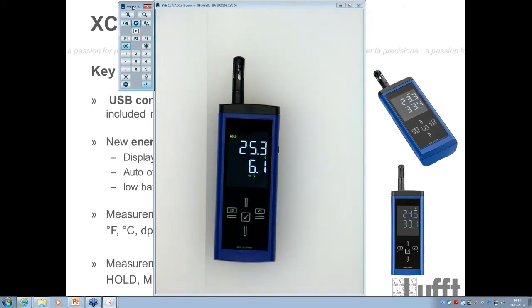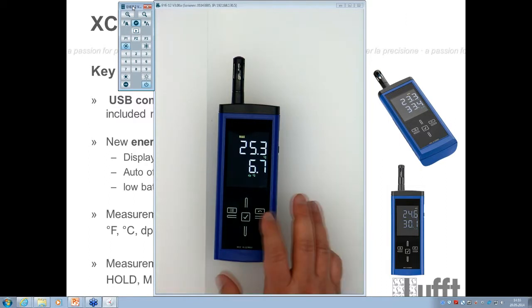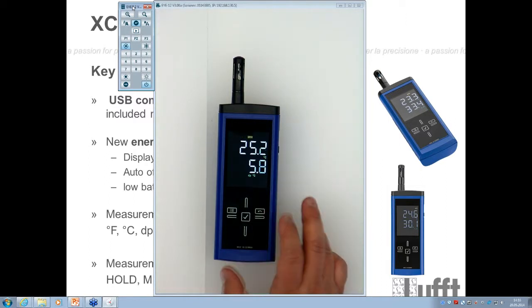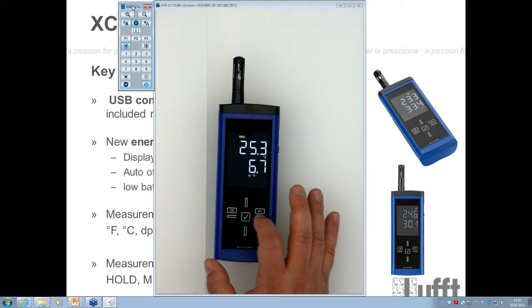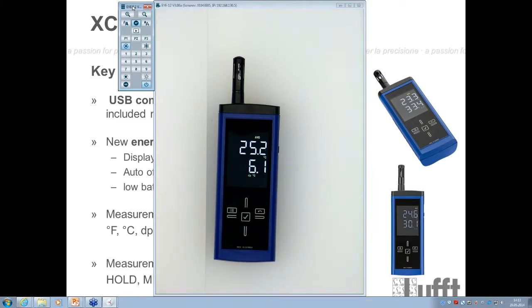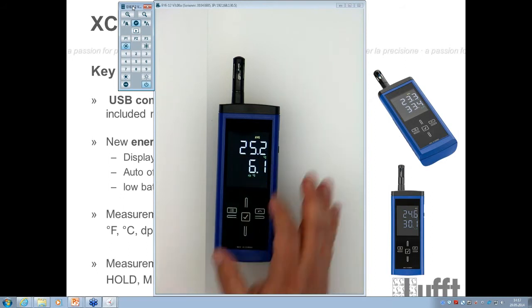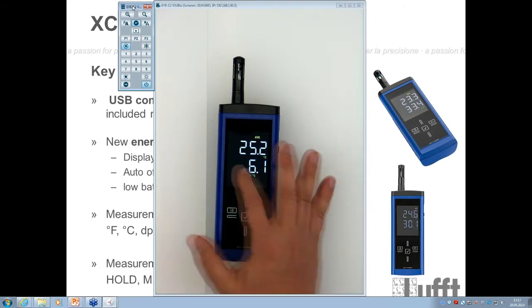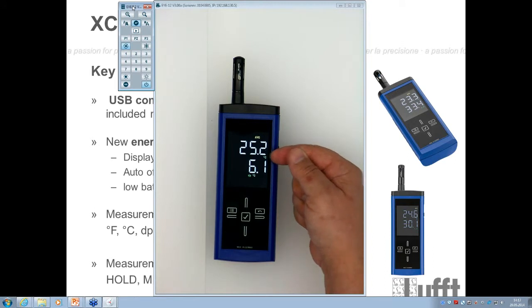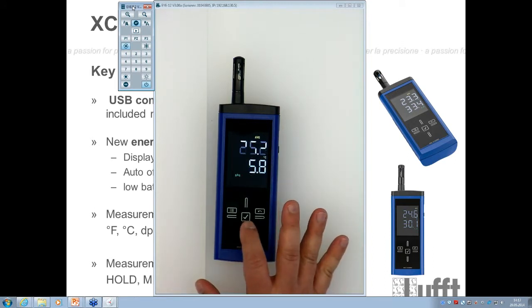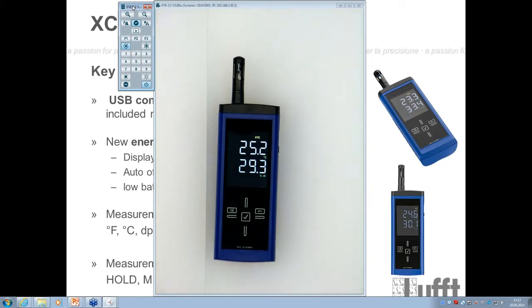Now you can go to hold, and now the actual value on the screen will be held. Or you want to enter or check the maximum value, then you go to the max indication with the left and right keys: min, average, or actual. Again, if you want to have the average, then this is the average value. You can also change again the combination here. In this case, I want to register, for example, Celsius degrees and the humidity. Then we go there, right? And now it's the average, and we want to start the cycle now.